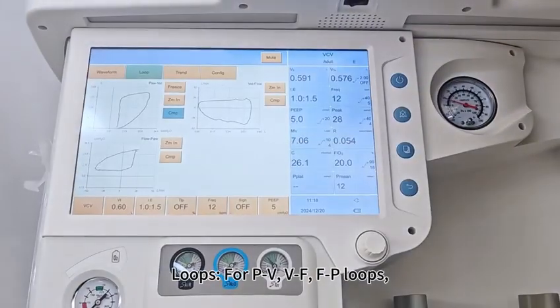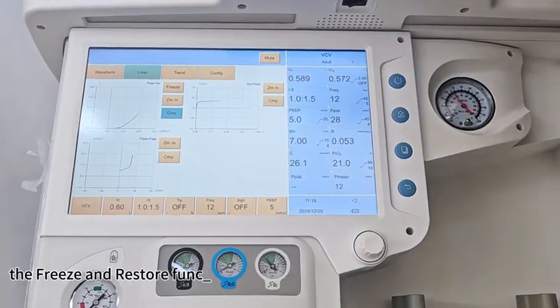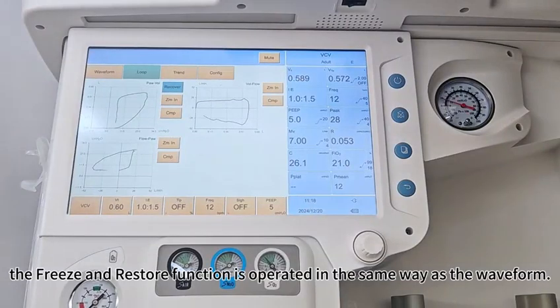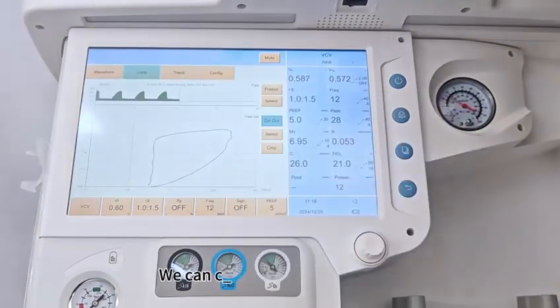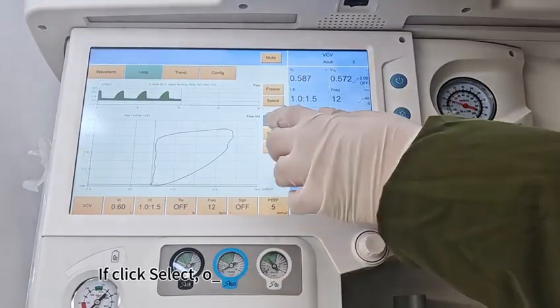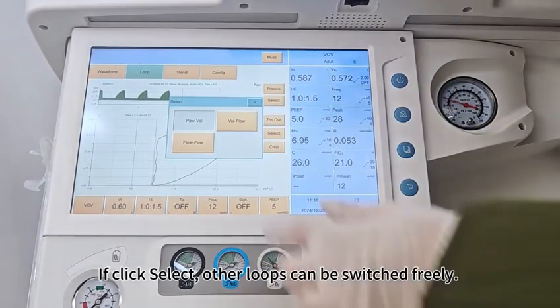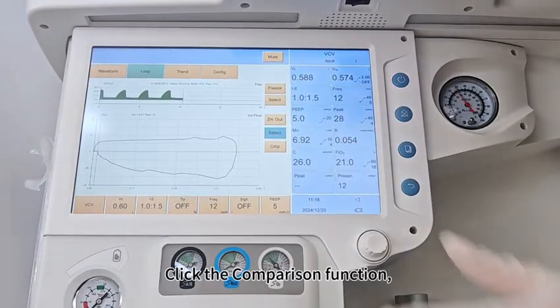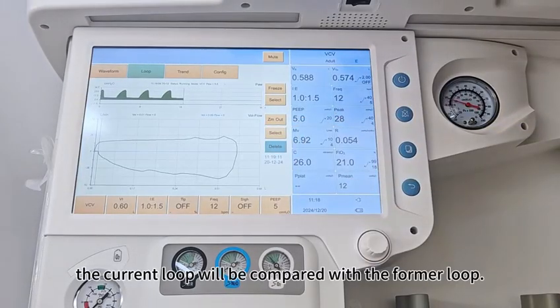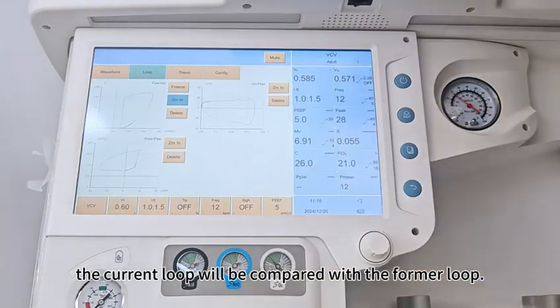Loops. For PV, VF, FP loops, the freeze and restore function is operated in the same way as the waveform. We can choose the zoom in function. If we click select, other loops can be switched freely. Click the comparison function, and the current loop will be compared with the former loop. If we click delete, the comparison will be cancelled.